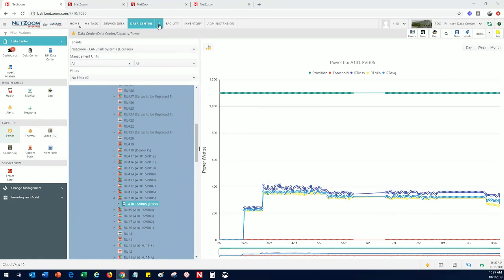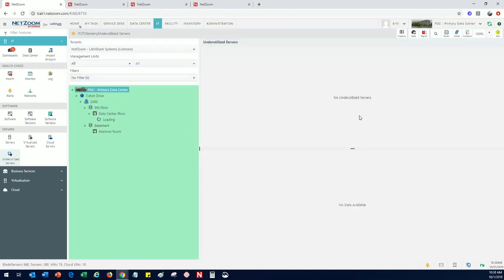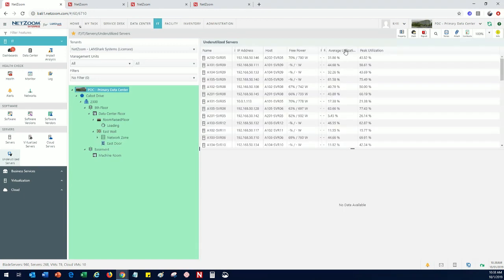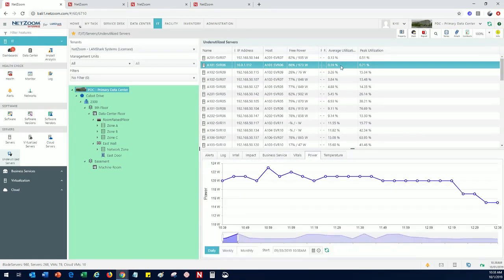Now I want to talk about those underutilized servers, those ghost servers. These are vampire power situations, guys, eating your bottom line alive. Any device discovered and being monitored in NetZoom, you can get a list of them by power utilization, by CPU utilization. Here we've got a server that at its peak is less than 1% CPU utilization, but for some reason it's running at 88% of power capacity, 973 watts. That server can be taken down, recommissioned, or decommissioned. Put this across your data centers, and as Curdy mentioned previously, 10 to up to 30% of servers in active data centers today are ghost machines like this, just eating away at your bottom line, at your power costs.